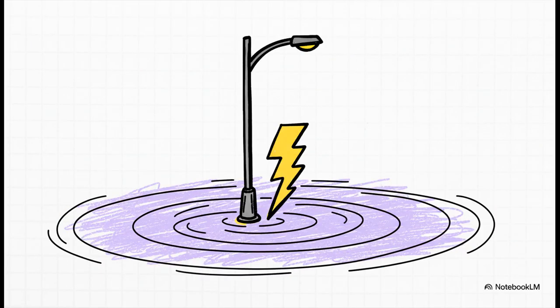Well, the whole problem boils down to something called earth potential rise, or EPR for short. When a big electrical fault happens and all that current dumps into the ground, it doesn't just disappear. It actually energizes the soil itself, kind of like charging it up. And this creates two really distinct and potentially deadly hazards that we absolutely need to get our heads around.